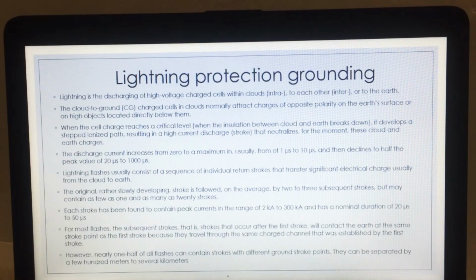Okay, this part is for the lightning protection grounding. Lightning is the discharging of high voltage charge cells within clouds, to each other, or to the earth. The cloud to ground, or CG, charge cells in clouds normally attract charges of opposite polarity on the earth's surface or on high objects located directly below them. When the cell charge reaches a critical level, when the insulation between cloud and earth breaks down, it develops a stepped ionized path resulting in a high current discharge or stroke that neutralizes for the moment the cloud and earth charge. The discharge current increases from 0 to a maximum in usually from 1 microsecond to 10 microseconds and then declines to half the peak value in 20 microseconds to 1000 microseconds.